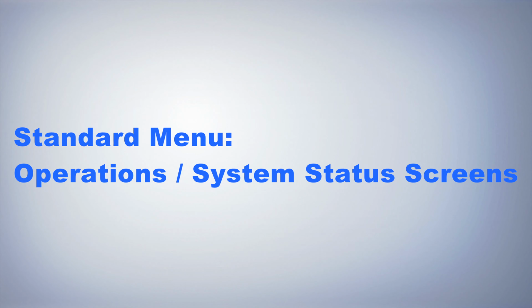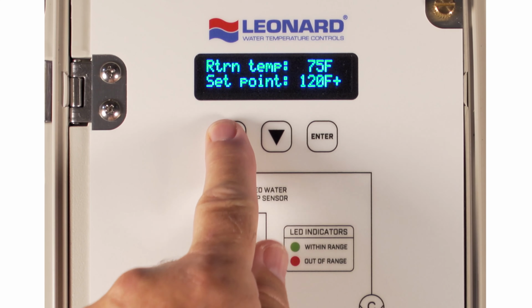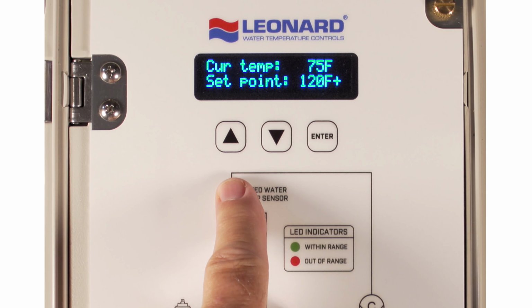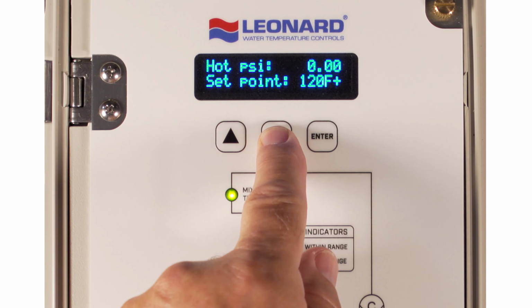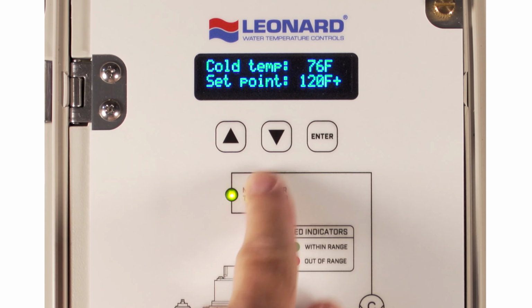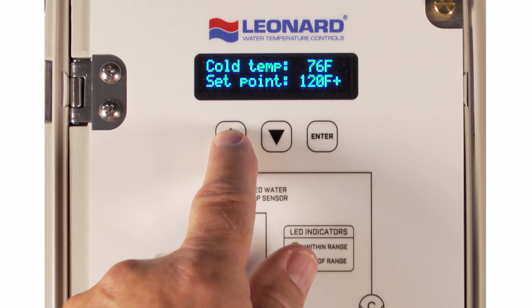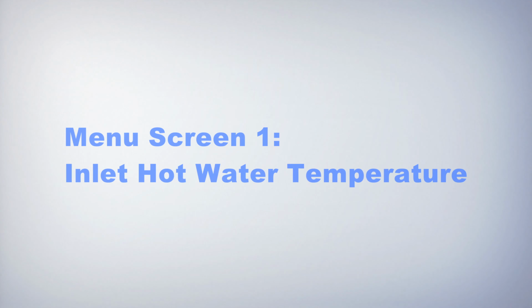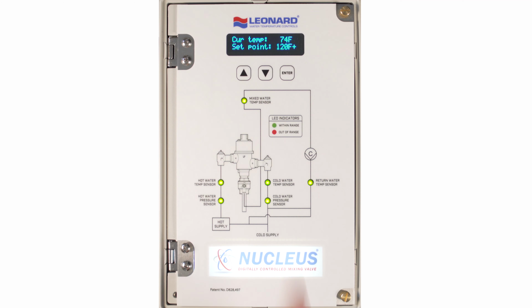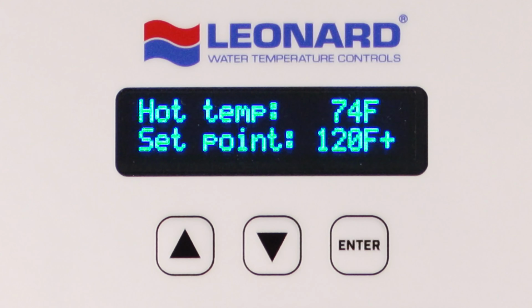Standard menu, Operations. Pressing either the up or down keys will allow a user to scroll through other data points, features, and options of the valve, and will show the following screens and features in order. Menu Screen 1. Inlet Hot Water Temperature. Pressing down one time displays Hot Temp, F or C. This screen displays actual hot water inlet supply temperature as measured at RTD T1 if the Nucleus is so equipped with the optional inlet temperature sensors.